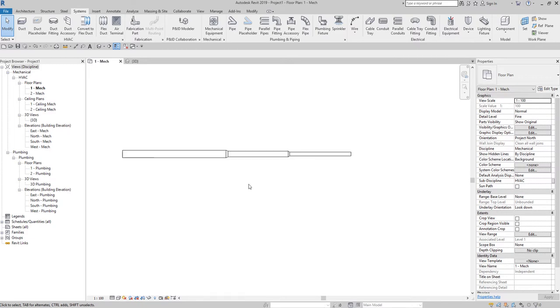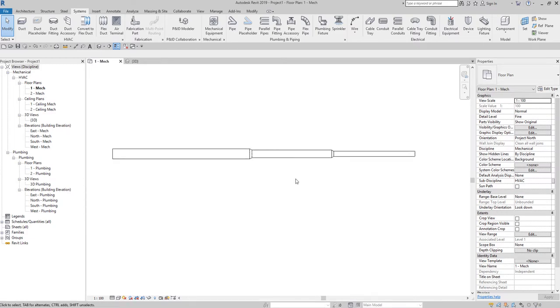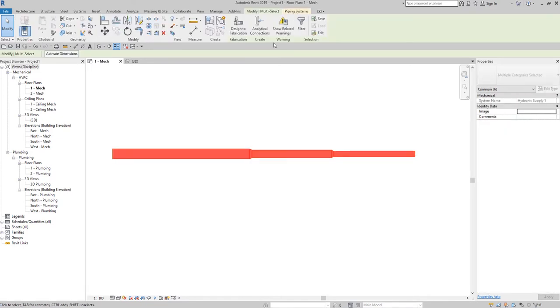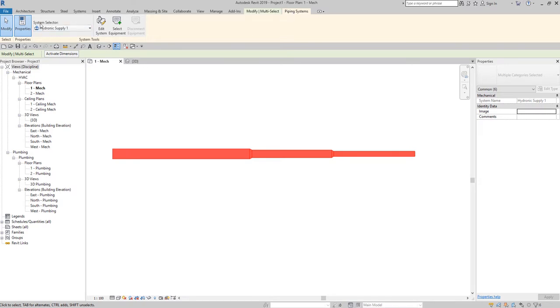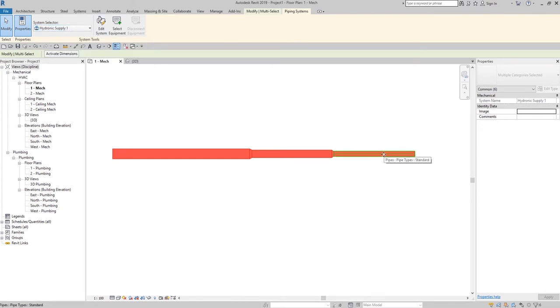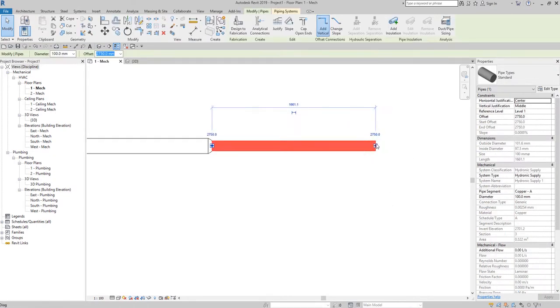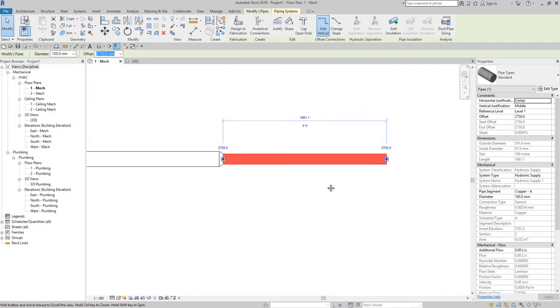In case you're having difficulty selecting an entire pipe network — because it's too long or the routing is complicated — you can use the Tab key to select the pipe network. Just hover your pointer over one of the pipes and press Tab continuously. Once it highlights the pipe network you want, click to select it. As you can see, the system is a Hydronic Supply. Let's say I want to change the justification from center to bottom.